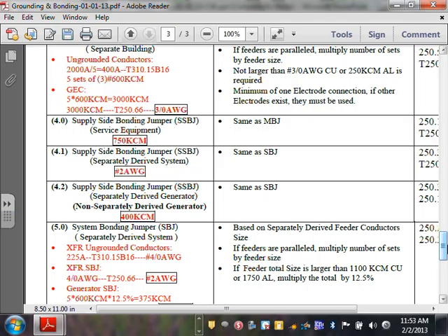That's assuming that the circuit breaker is not at the generator, and the circuit breaker goes right inside the switchgear. So we're pulling all the conductors from the generator, which we can, all the way to the parallel switchgear, landing it on the load terminal of the circuit breaker. Now in a case like this, that wire will be a supply side bonding jumper. Typically the breaker is on the generator, if you don't parallel. So if you're pulling it as paralleling switchgear, you don't put a breaker on the generator. You don't want to interrupt it anyway. You're paralleling. If you put your breaker on the generator, that's a different story.